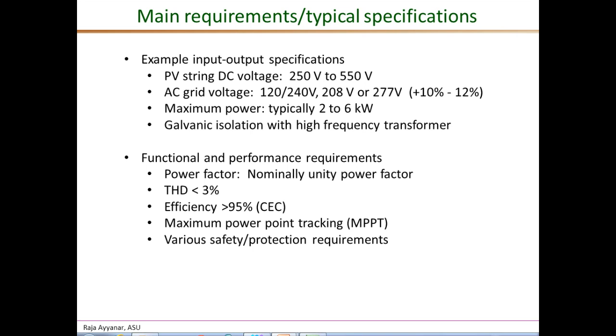The waveform quality of the current that is injected into the grid has a very stringent requirement. This is given in terms of the total harmonic distortion THD allowed in the line current, which is typically in the less than 2-3% range for inverters of most major manufacturers.